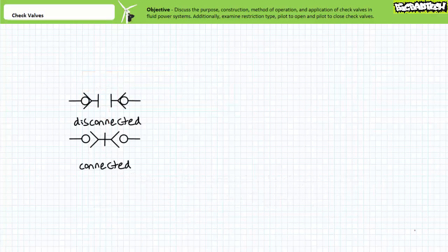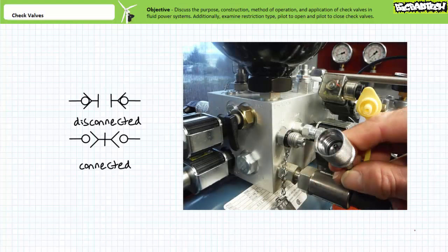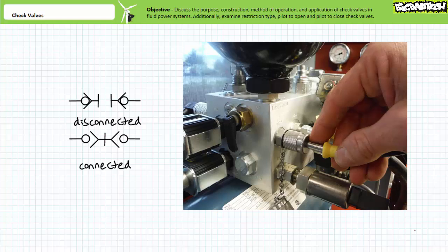Consider a quick disconnect with check valves that allow the connection of a portable manometer to a push-to-connect inspection port. When disconnected, the check valves on each quick disconnect are closed and allow the system to function as intended without leaking. When connected, the quick disconnect pushes both balls off their seats and conducts fluid from the system to the portable measurement apparatus.